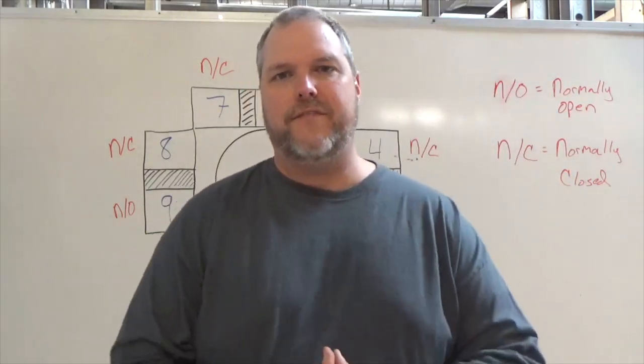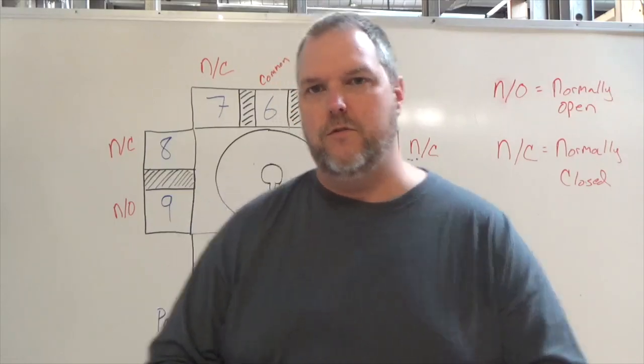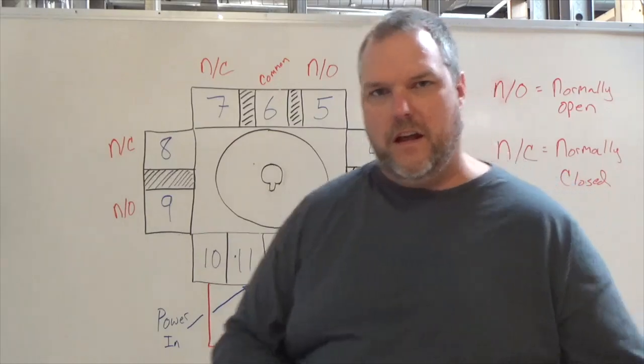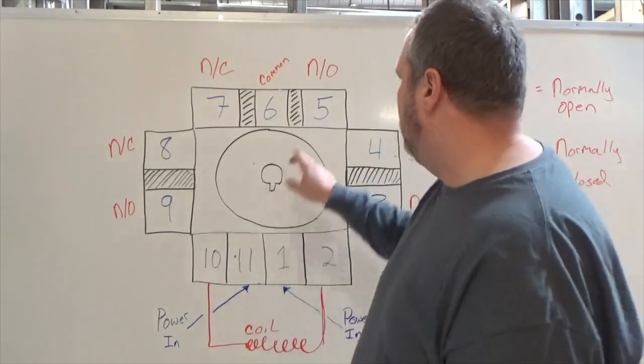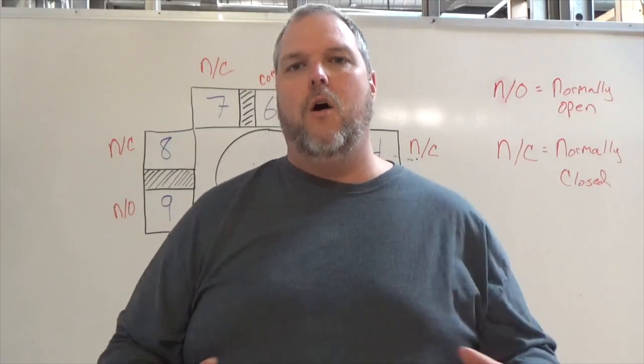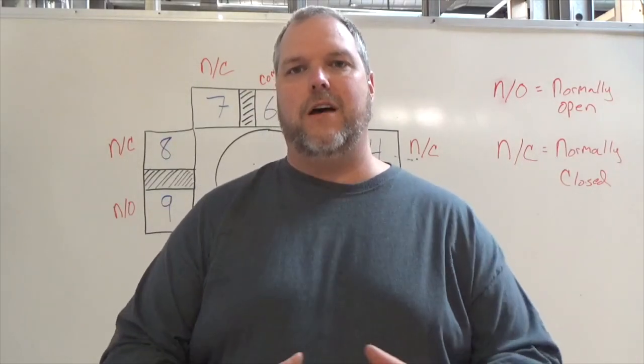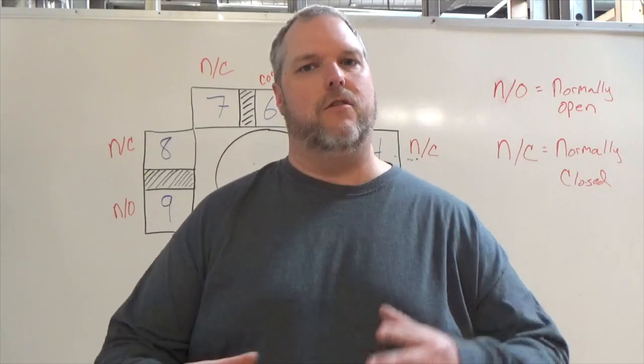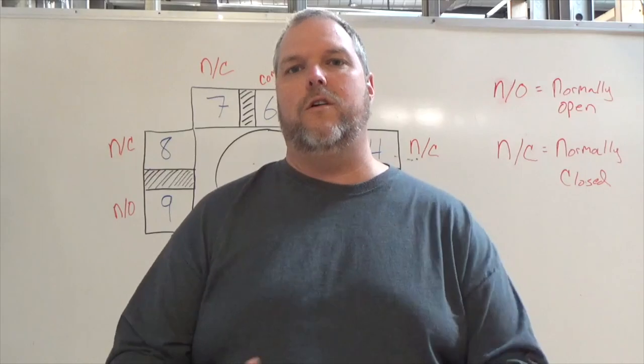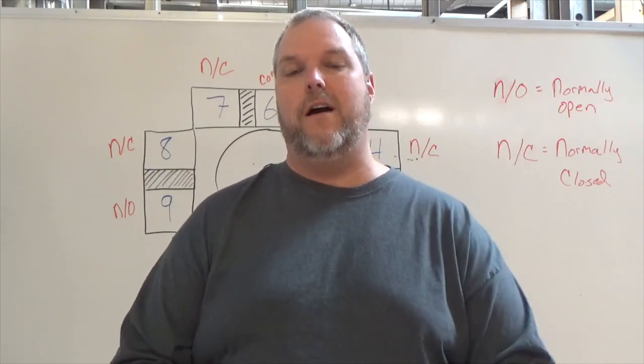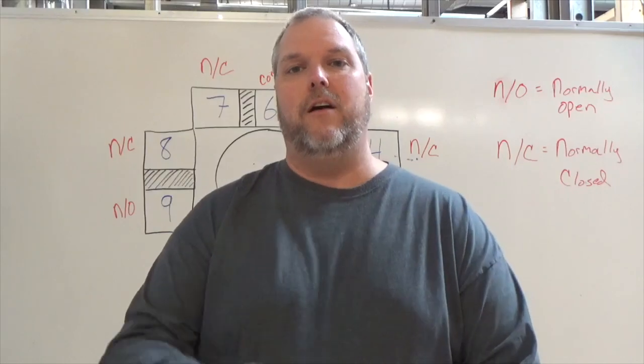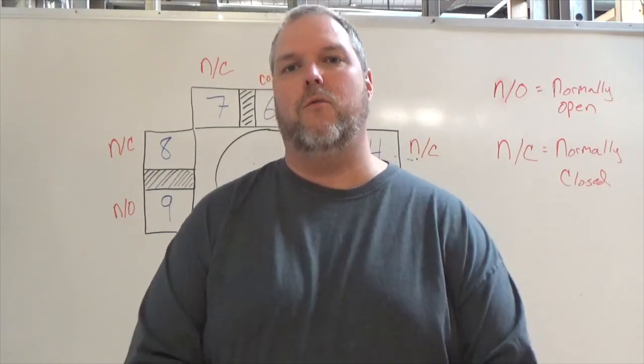In an off delay, the 7 pin is not used, so this pin is not used at all. In an off delay, you're going to use your 5 and your 6 terminal as what we call a trigger. We're going to do videos on off delay, so don't really worry about it. You're going to probably refer back to this video once you start to see an off delay and how they're wired and different opportunities that we can make that work so that you get a better understanding of typical motor control wiring.